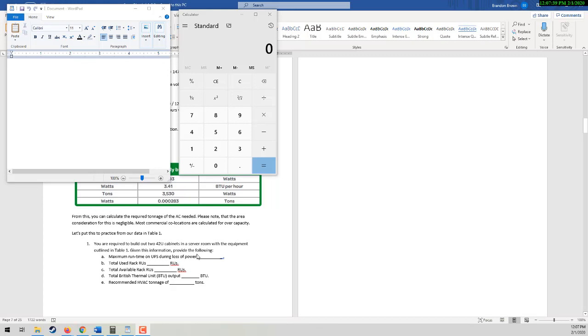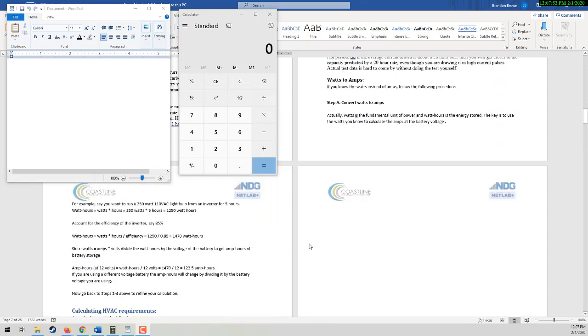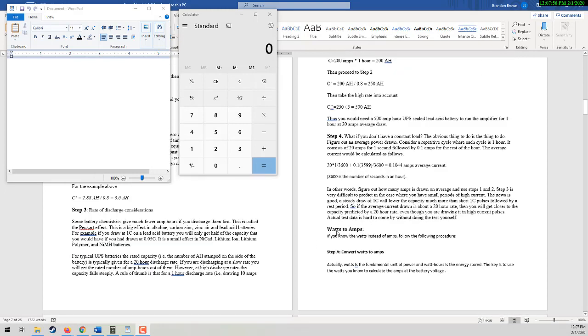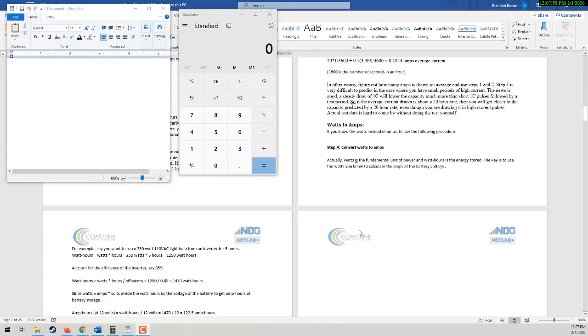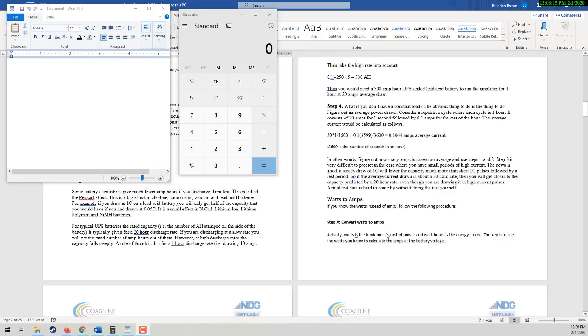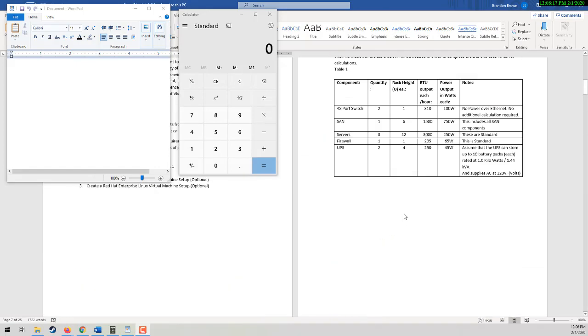The first question is probably the hardest question in the entire lab because we have to figure out what the run time of the UPS is going to be. So in order to do that, here at the watts to amps, these calculations are very critical. What we have to pay attention to is watts equals amps times volts. I give you the watts of each individual item and I give you the volts, the maximum number of volts, which is 120. In actuality, I'm making this a little simpler because each individual component would have its own voltage draw on it. I'm just going to go with the output of 120 to make the calculation a little simpler.